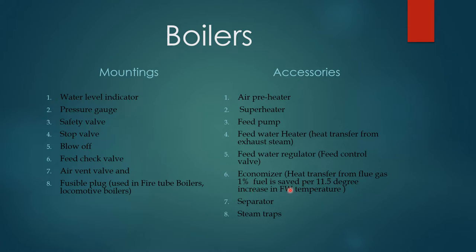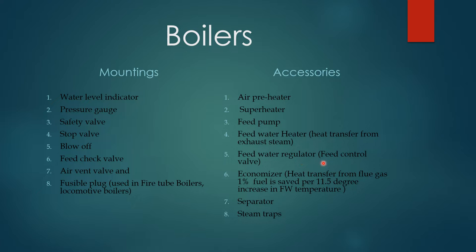Normally 1% fuel is saved if the temperature increase is around 11.5 degrees centigrade. So if you use a feed water heater or an economizer you can save fuel. Other accessories include the feed water regulator, that is the feed control valve, steam separator, and steam traps.